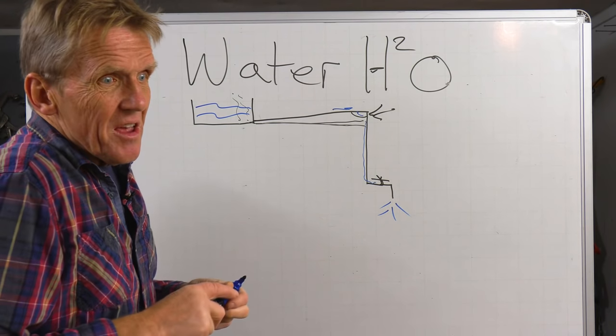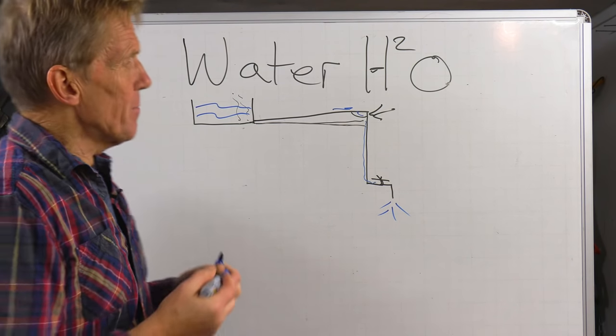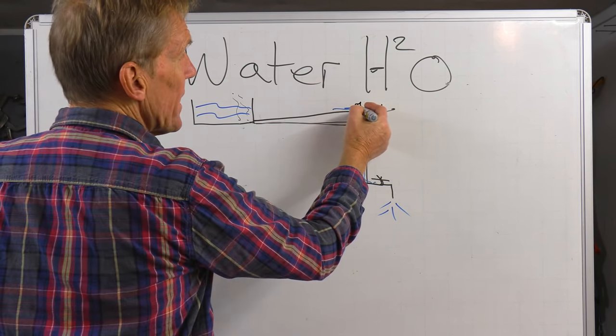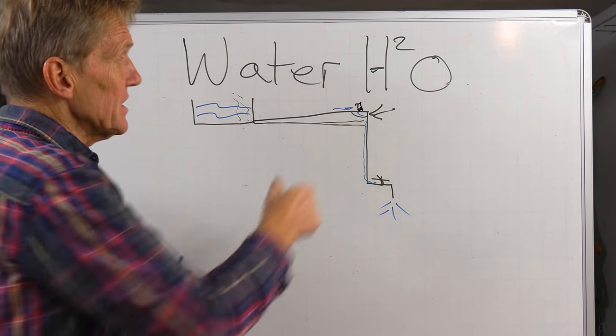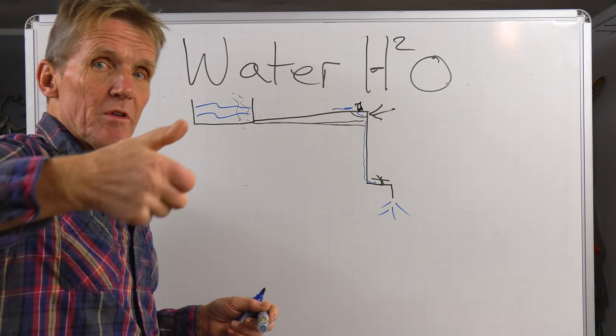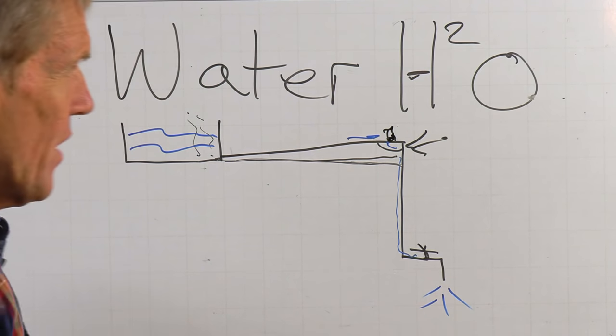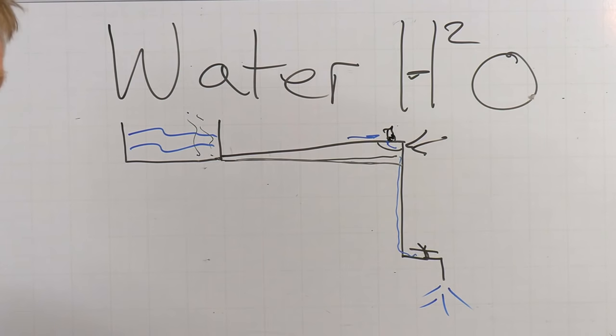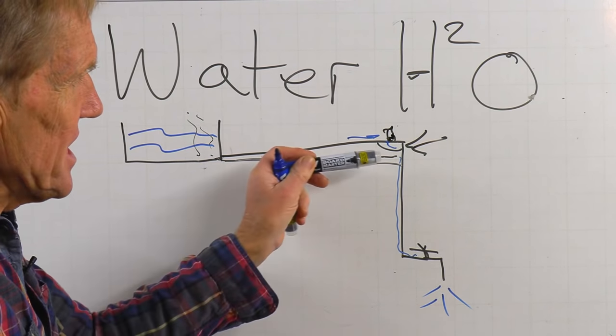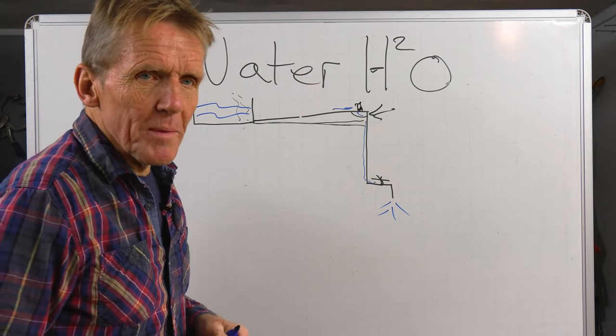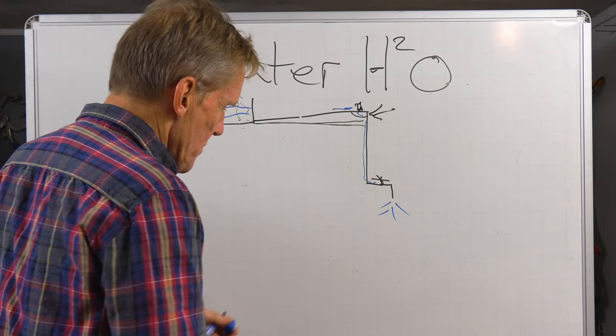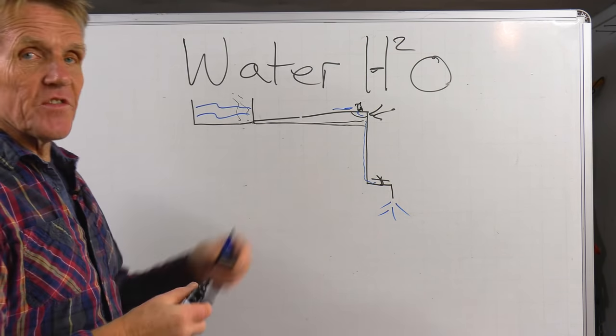Now, if we do get airlocks and, you know, the pipe's laid, we're not going to relay the pipe. What we can do is put an air valve in there, an air release valve in there, to take out that little bit of air. You can use that with a radiator key, or sometimes you get an automatic air valve, which simply goes in the top, and you bleed that off, and it just collects the air and releases it automatically. They weep a little bit, though, so I wouldn't leave them open, but they're a good device for that.